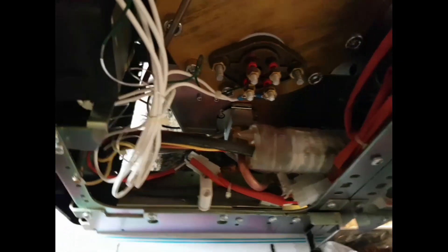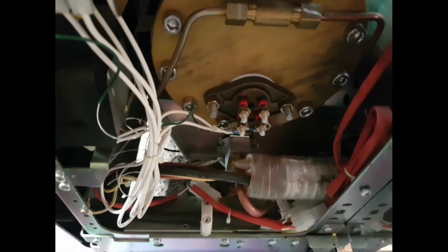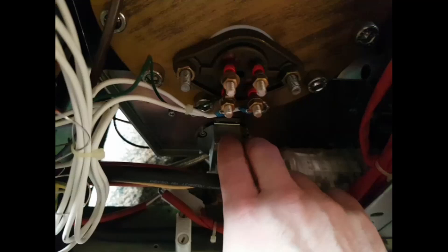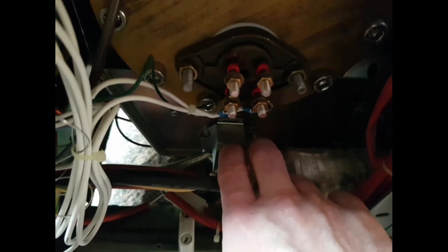So here is the business end of the burner. Behind this fitting lives a gas jet that governs the maximum flame size. And then this adjustable aperture goes back and forth. And this air space dictates the air and fuel mixture and therefore the emissions. And when I'm talking about emissions, any kind of device that consumes propane or natural gas is going to create carbon monoxide. And so the air fuel mixture is extremely important to prevent people from getting carbon monoxide poisoning.